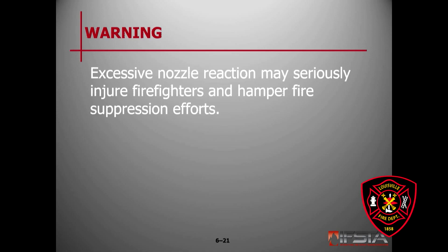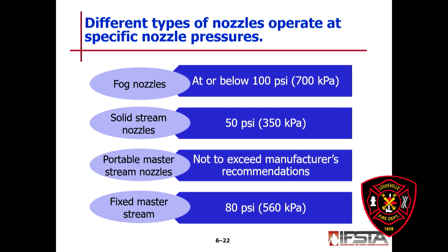Excessive nozzle reaction may seriously injure firefighters and hamper fire suppression efforts. Putting too much pressure on the line can injure the firefighter — you can make the job inside a burning building much easier with the right pressure on the line. Different nozzle types operate at specific pressures: fog nozzles at 100 PSI, solid stream nozzles at 50 PSI, and fixed monitors at 80 PSI.